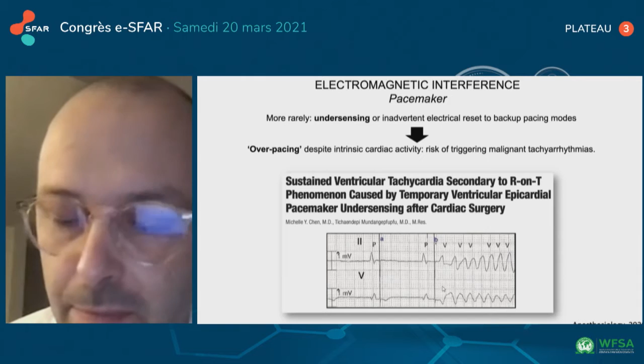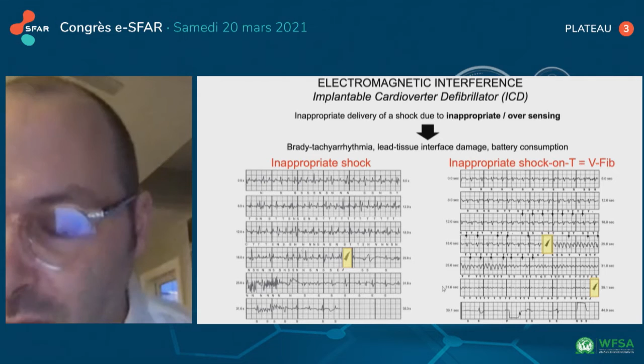Considering implantable cardioverter defibrillators, the main problem that we have with interference will be oversensing of the device that will produce an inappropriate shock. Inappropriate shock can be responsible for damage in the myocardium and for tachyarrhythmia, particularly if, of course, the shock falls on the T wave, and also battery consumption. This is very important, because consuming the battery of a device may reduce the lifetime of that device. And we know that it may be complex for cardiologists to exchange this type of device.